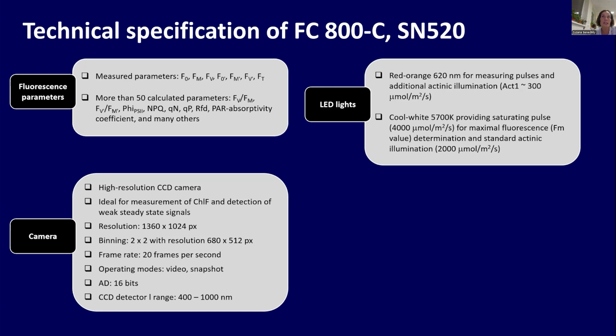The LEDs you have in your system come in two colors. One color is red-orange. Approximately the peak wavelength of these LEDs is 620 nanometers. These LEDs provide measuring pulses and actinic light. I will explain later. This is called actinic 1, and it's a weak actinic light. The maximum of this actinic light is 300 micromoles per square meter per second. Another color of LEDs, the second pair of LED panels, provides white illumination.